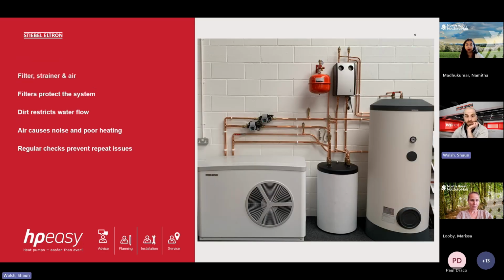So filters, we look at filters, strainer, and air. Two of the biggest causes, generally, these happen during commissioning, but they can happen over the summer months. So, are dirt and trapped air within the system. Trapped air generally will get caused during the summer months when no one's had their heating on and the system has been sat idle for 3 or 4 months, and it hasn't run any water through the system. Generally, what will happen is the system pressure will reduce over those couple of months. The water will be sat stagnant and not flowing. And then what happens is you get air in the system as well. So that can cause issues as well.